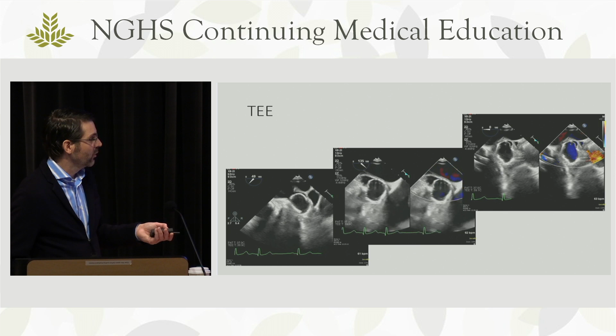You can see the device, the 27 millimeter device, is pretty elongated. It has the same issue on the back side of the device. There's a lot of dead space here, and it's all the way up against the wall. There's nowhere to go deeper. So we were talking to each other during this case, and we were saying, well, what are we going to do with this? If you go bigger, you're going to make more dead space. It's going to elongate. If you went to a 31, it's going to make it even longer.